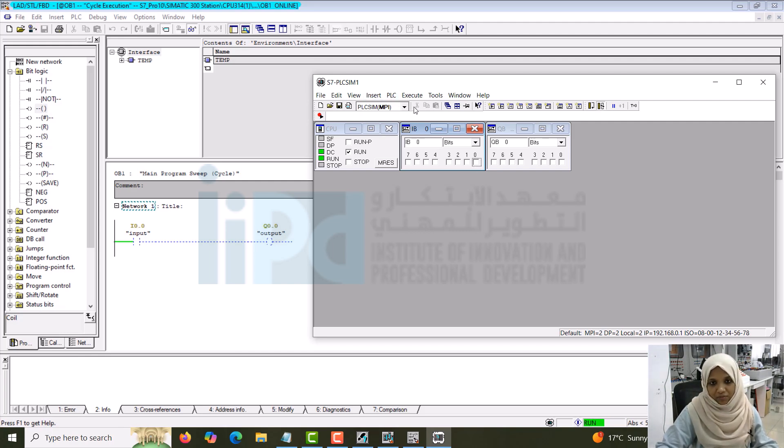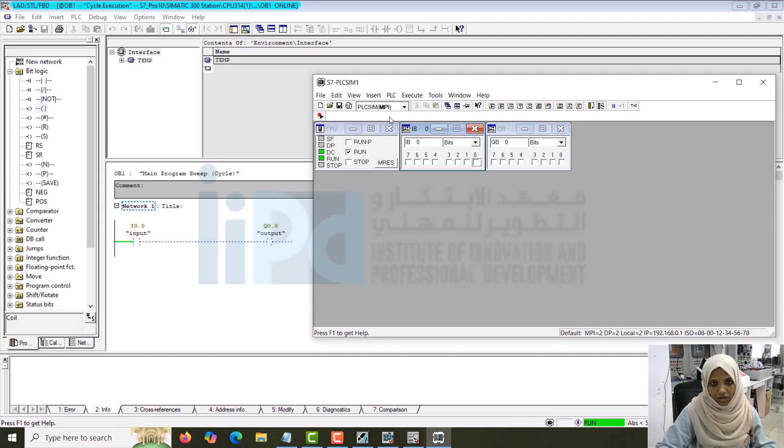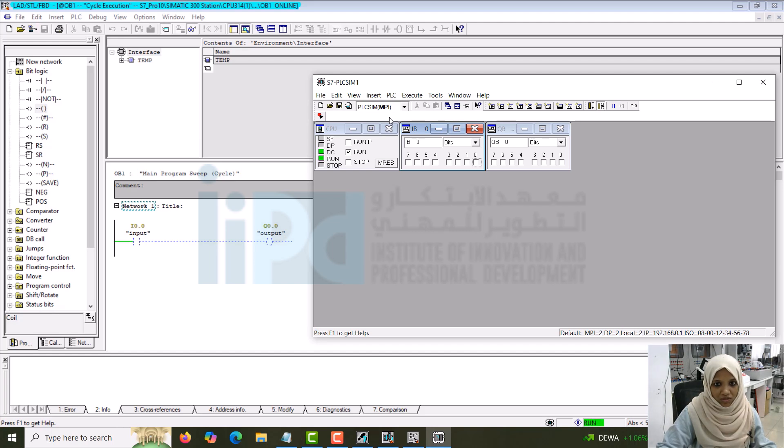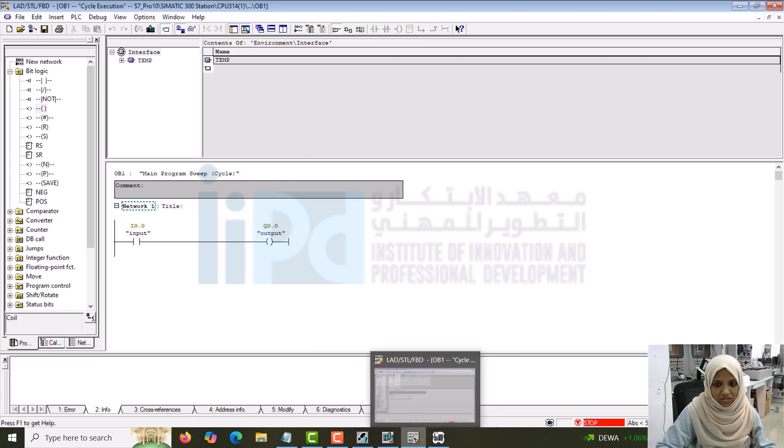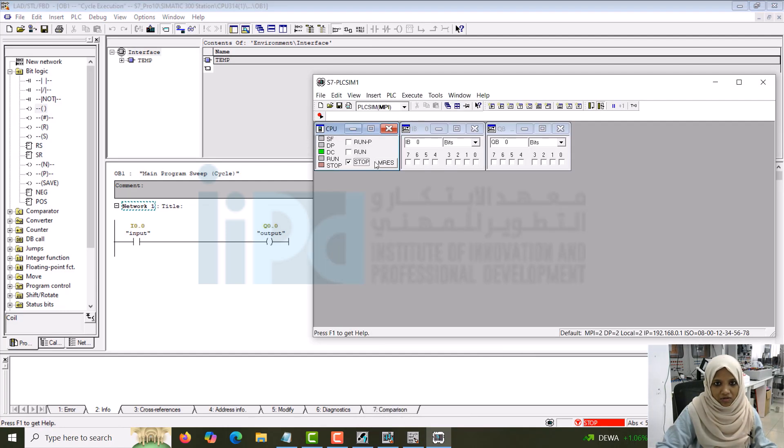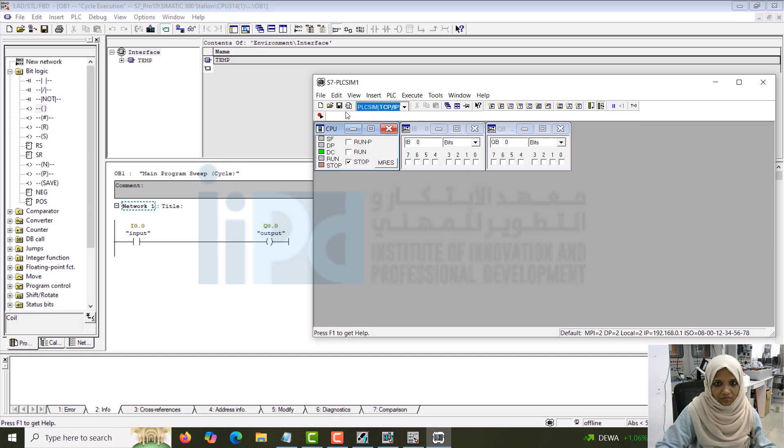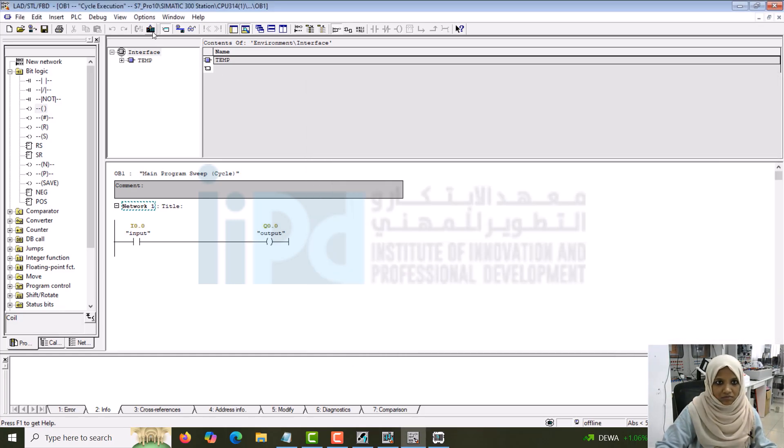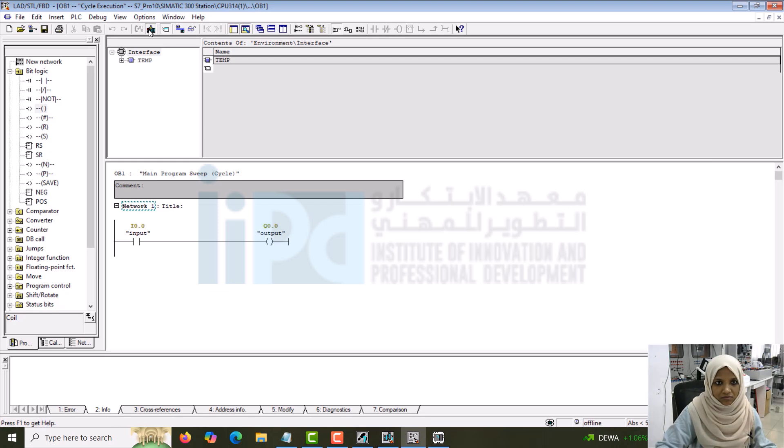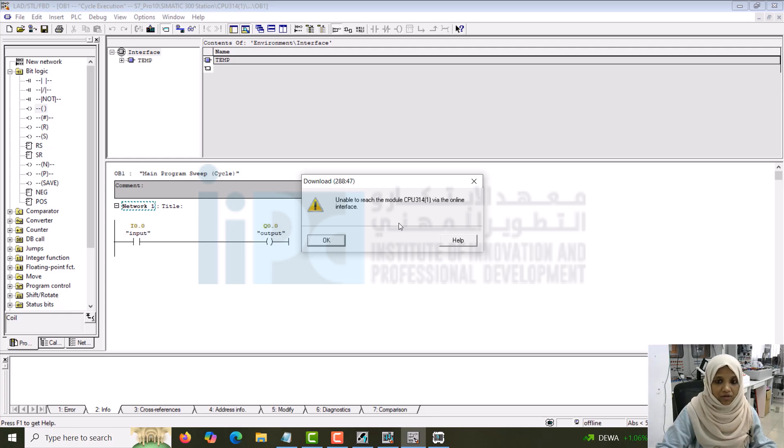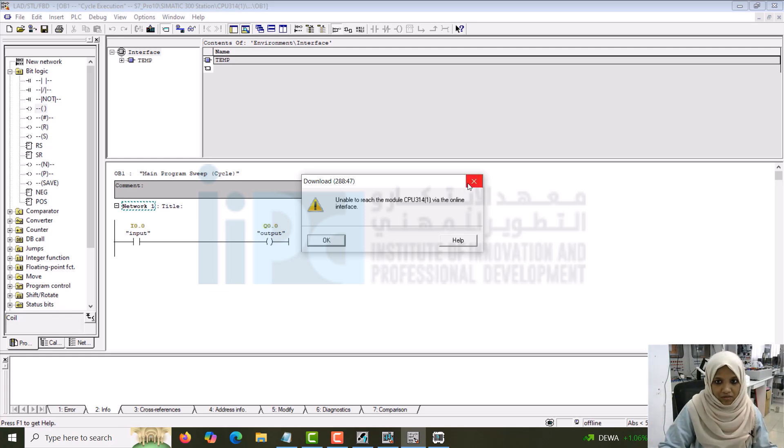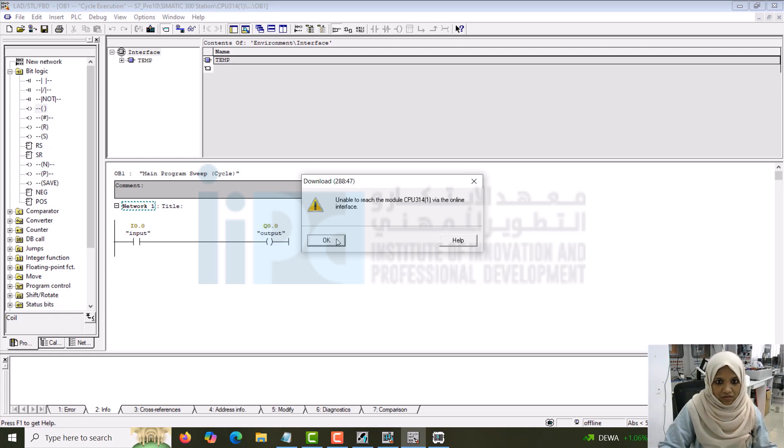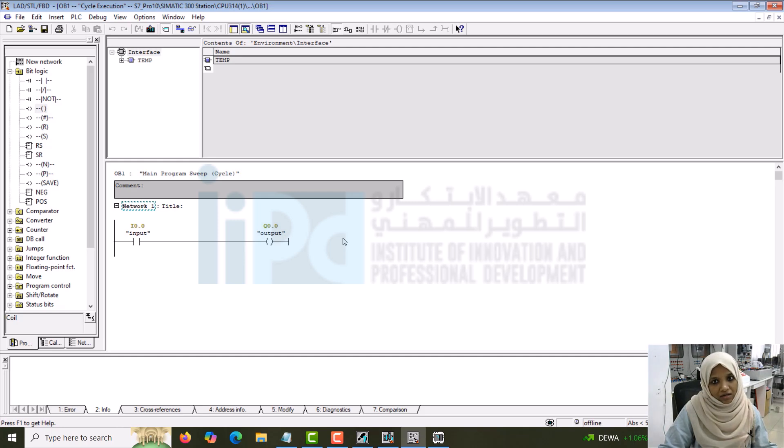Make sure that usually people will have a confusion or they will get error on this part. It might be default. It will be like TCP/IP. If the model is not supporting TCP/IP, it will show error. It will show as unable to do the connection. Let's check. For example, if I go to stop and go offline and then change the thing to TCP/IP, see it will show this error, unable to reach the module through online interface. This can happen in the hardware module also. Make sure that there also you are choosing the correct PG/PC interface. PG/PC interface means the communication between the programming device and the PC.